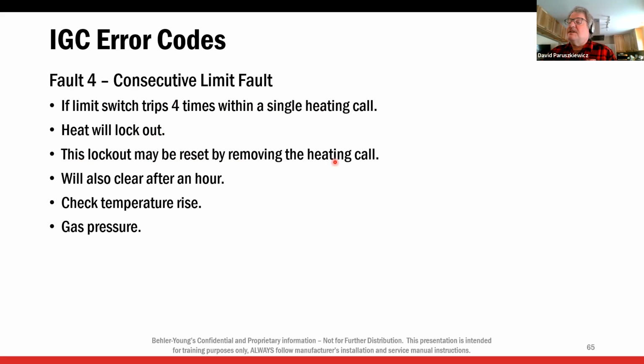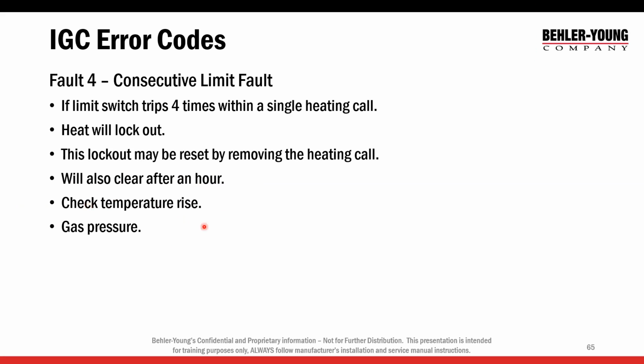This lockout may reset by removing the heating call. So if you take the heating call off, turn the temperature down, turn it back up, it will clear. It will also clear after 1 hour. But if it's been off for an hour, 16 degrees outside, it's cold, so you're going to get called on this. If this happens, like we just talked about, check your temperature rise, check your gas pressure. Limit trips are due to overfiring, underfiring, not enough airflow. That's generally the things that are causing it. Or stratification, high return air temperature.